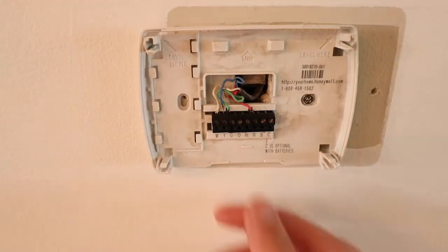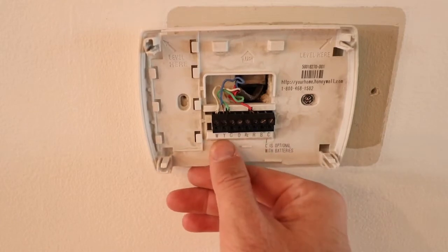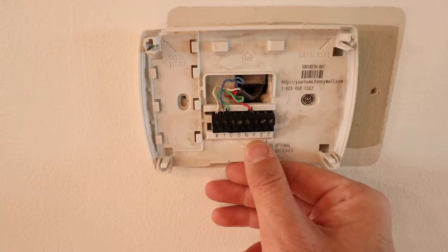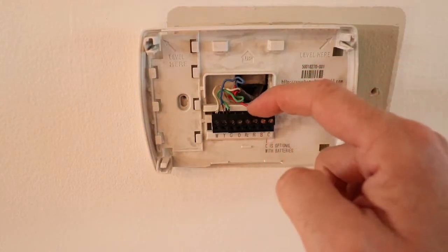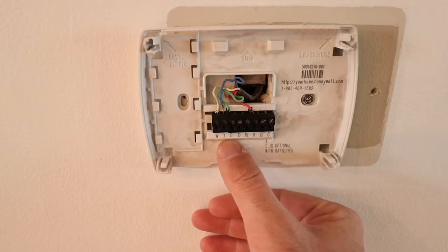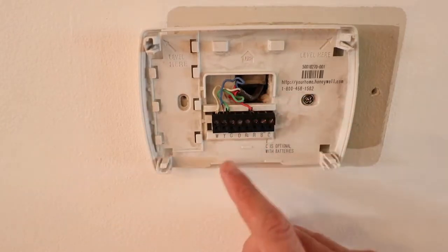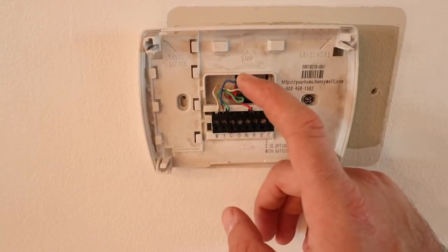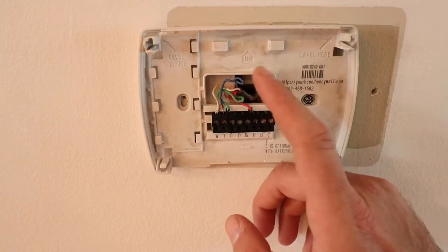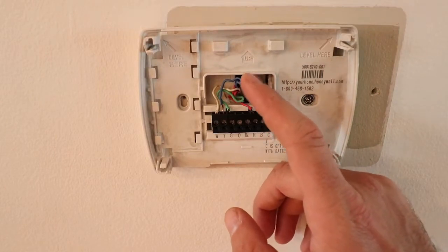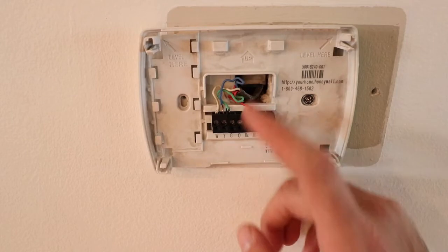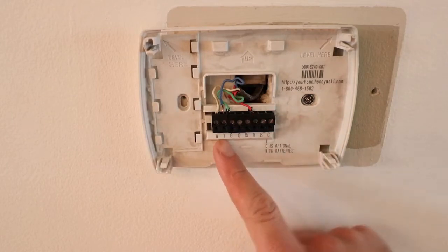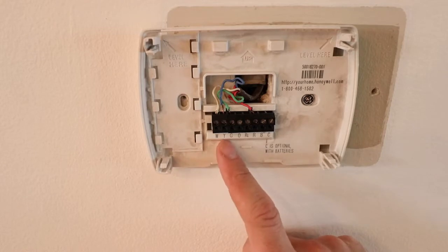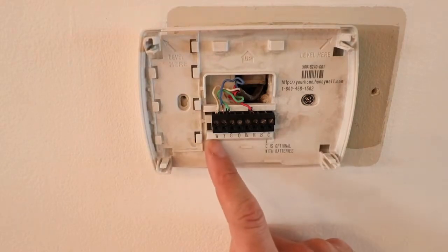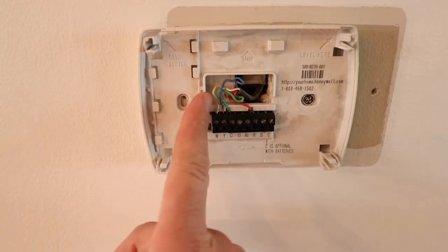The other wires we have here are the R wire, the G wire, the Y wire, and the W wire. The R wire is the power wire—that's this red wire coming in here. The G wire is the fan control wire, the green wire. Then we've got the Y wire, which activates the air conditioning compressor—ours is this blue wire; sometimes it's yellow, or it may be an entirely different color, but you know what it does by the designation on the existing thermostat. The W wire is the call for heat, or the furnace in our case, and that's this white wire here.